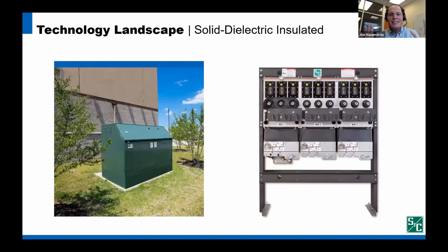The most recent sealed submersible switchgear technology is solid dielectric switchgear, like the Vista SD product that you see on the page here. Solid dielectric solutions have been developed over the last 15 years due to both a market pull reason as well as supplier push reasons. Beginning in the late 90s, there has been a steady market pull that SF6 could be phased out very abruptly, and users would need a no maintenance alternative to SF6 insulated gear. That was a pull that started in the 90s.